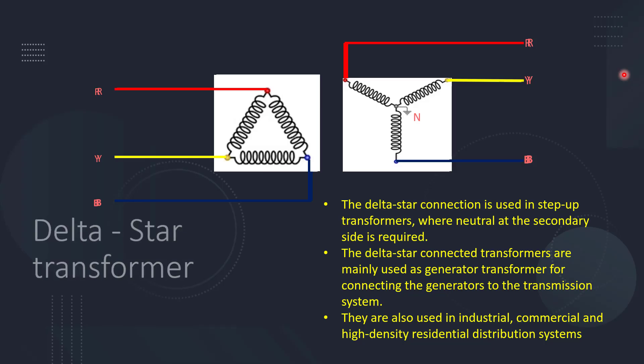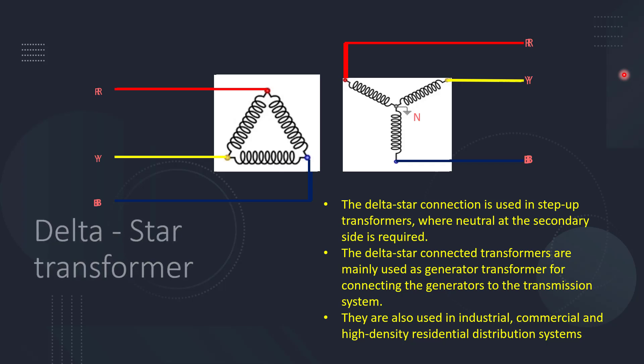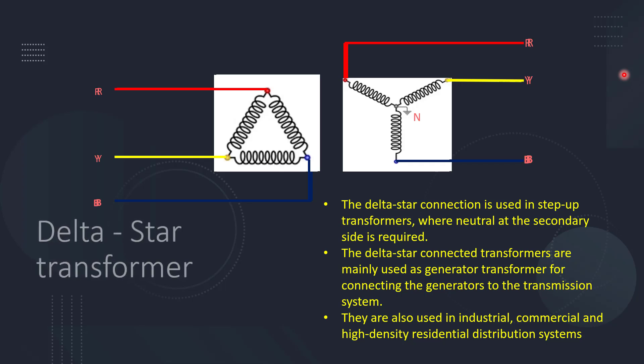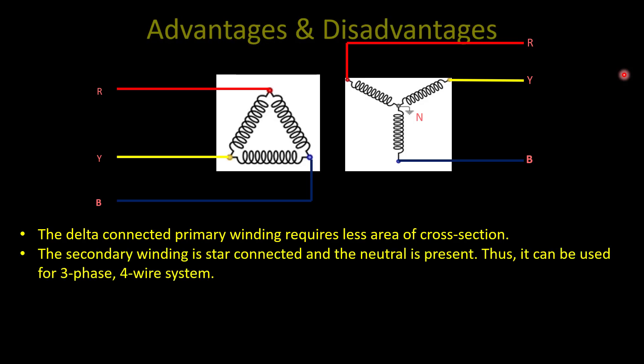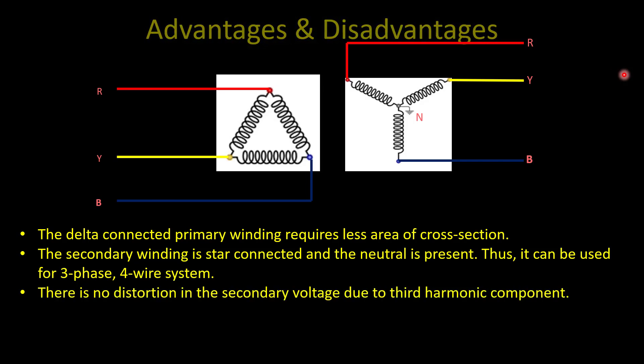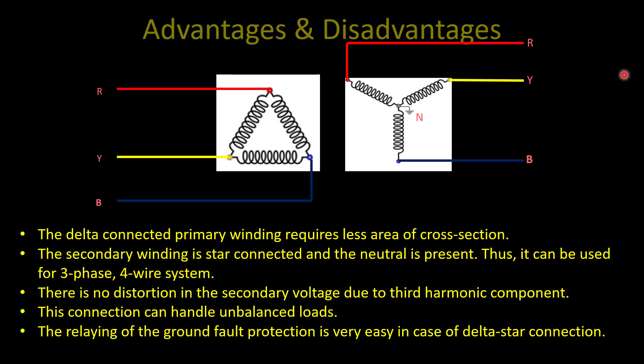Another one is delta-star transformer. The delta-star connection is used in step-up transformers where neutral at the secondary side is required. Delta-star transformers are mainly used as generator transformers for connecting generators to the transmission system. They are also used in industrial, commercial, and high-density residential distribution systems. Advantages: the delta-connected primary winding requires less cross-section area. The secondary is star-connected with neutral present, so it can be used as a three-phase four-wire system. There is no distortion in secondary voltage due to third harmonic components. This connection can handle unbalanced loads and ground-fault protection relaying is easy. This is the most commonly used step-down transformer and can be seen in gated societies or apartment complexes.